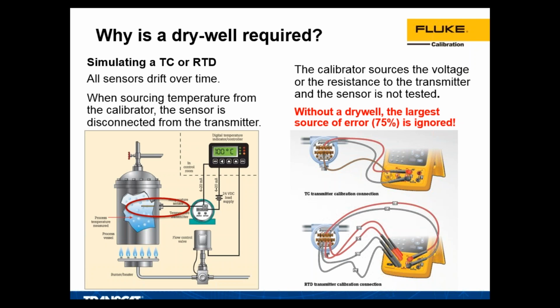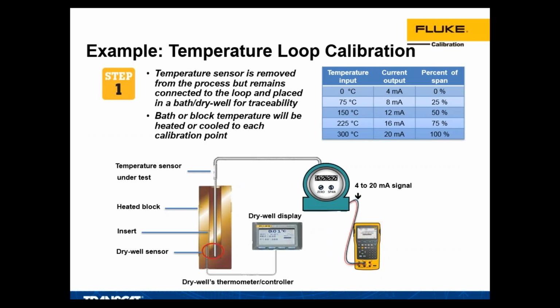And so you can kind of see if I got to disconnect that sensor and hook up my 754 to it, like you see over on the right, I'm not even testing the sensor. It could be drifting, it could be experiencing all kinds of issues, and I wouldn't even know it. So that's why we want to include the dry block. The dry block is going to help us include the temperature sensor in the calibration.